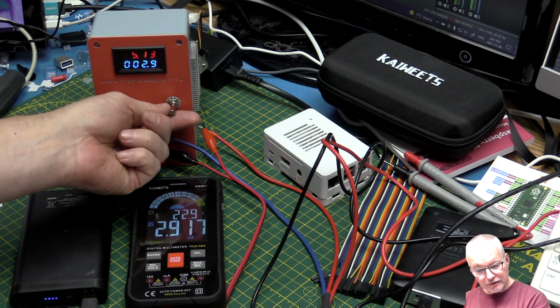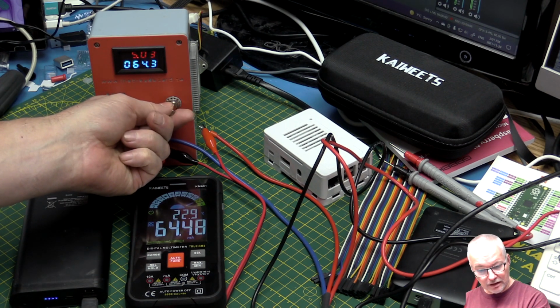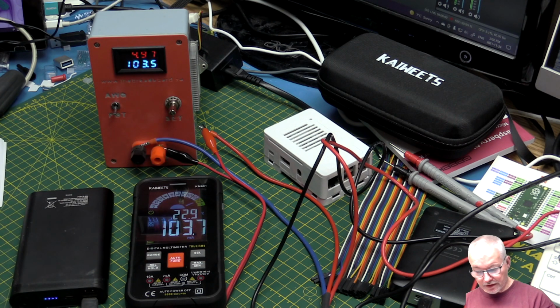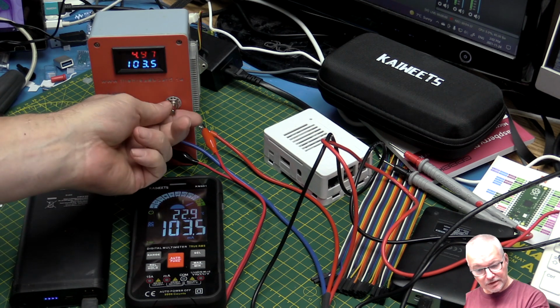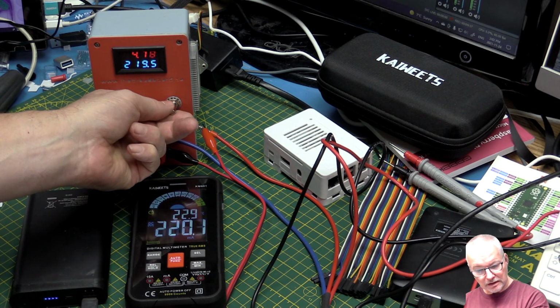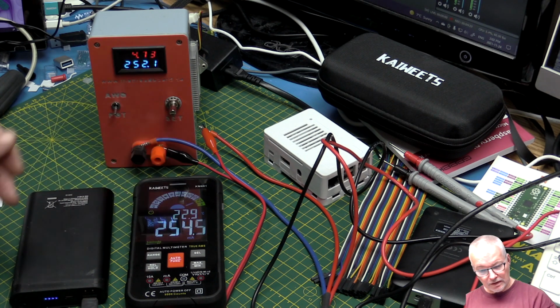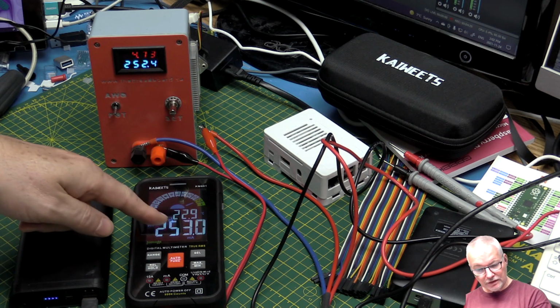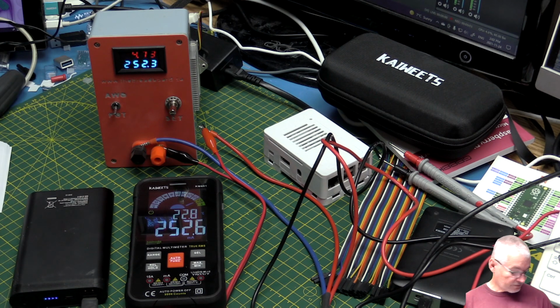Let's go up carefully, I don't want to go over the fuse rating. 100 milliamps, close enough—103, 103 on the milliamps. Let's go up to 250-ish. So 252, we're reading 253, still close enough.